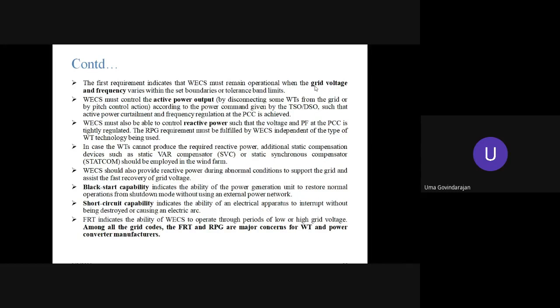So reactive power control is a major issue. Once again, I'm strengthening the statement: reactive power control is a very, very important point one has to take care of while interfacing wind electric generators to the electrical grid. Next one, black start capability indicates the ability of the power generation unit to restore normal operations from shutdown mode without using an external power network. So the wind turbine system should be self-sustained. It should not depend on the grid power to restore normal operation after a blackout.